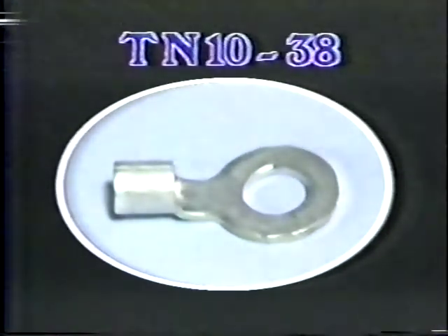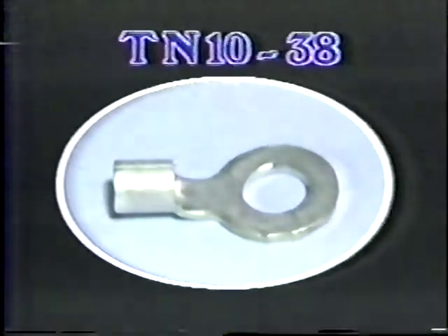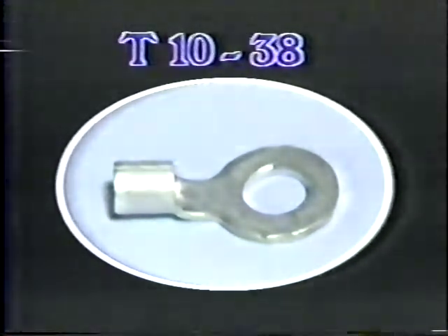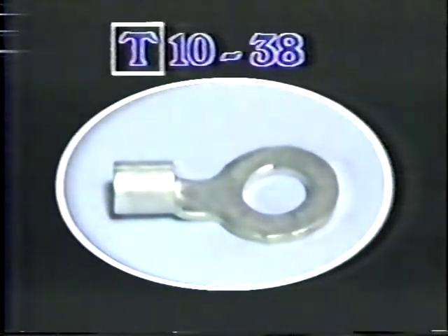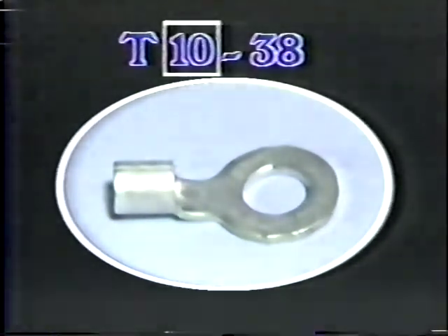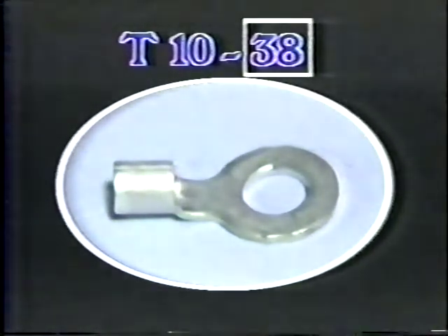Uninsulated terminals are specified in a similar manner to our insulated terminals. However, the insulation digit is omitted. In this example, we have an uninsulated terminal that will handle a number 10 gauge wire. As indicated, this terminal will accommodate a 3/8 inch stud.